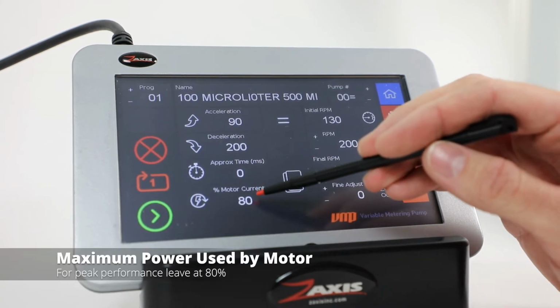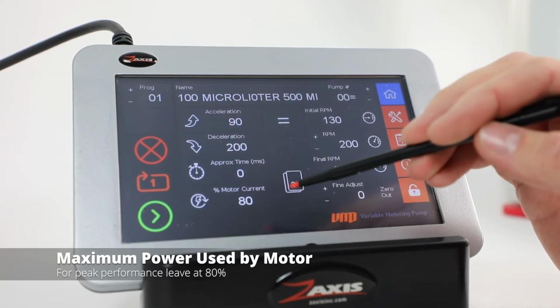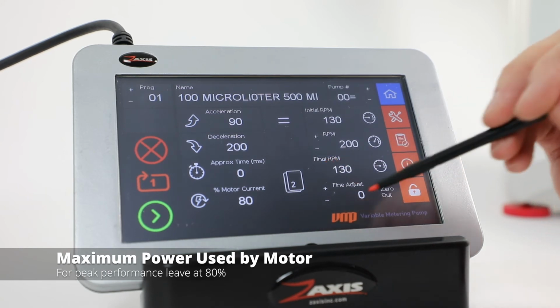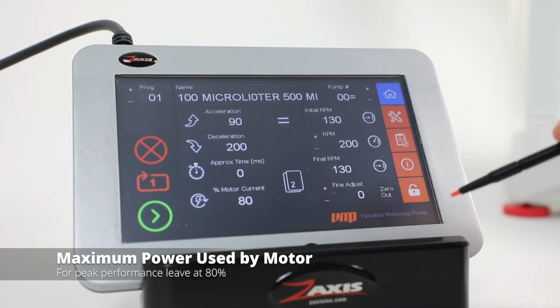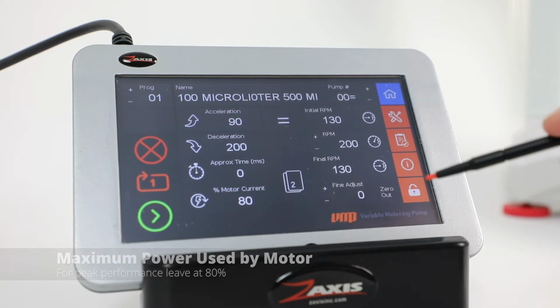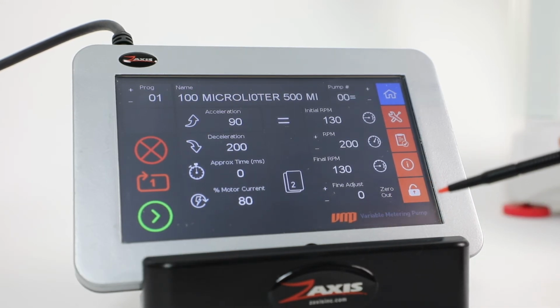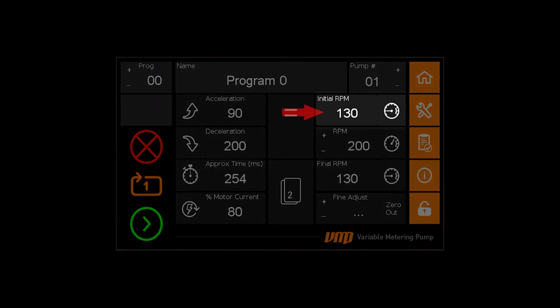So here we have the percentage of motor current. This is the amount of maximum power the pump will use to turn the motor. We recommend you leave this at 80%. Any higher can cause the motor to overheat and will eventually degrade the pump over time. So here we have the initial RPM. This is at the beginning of the dispense. This is how fast it's going to reach the actual RPM right here. And then the final RPM is at the end of the dispense.